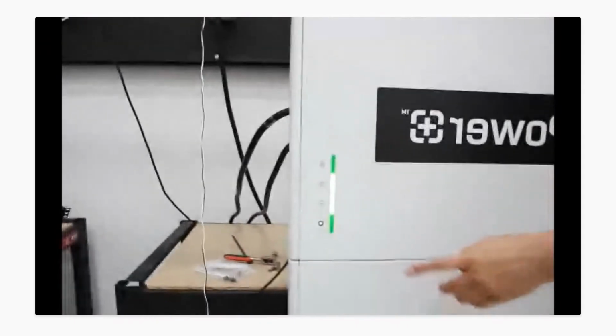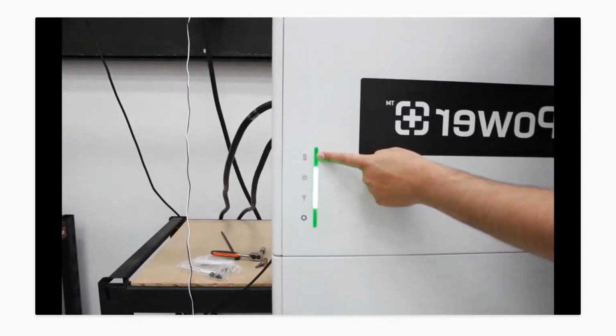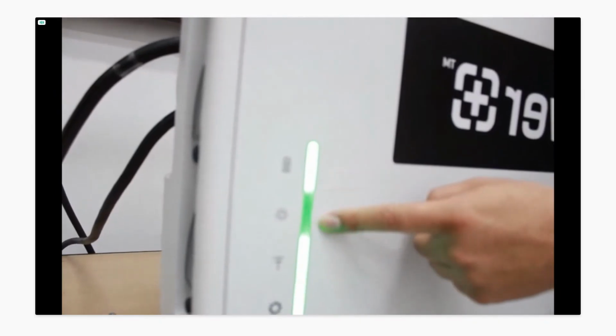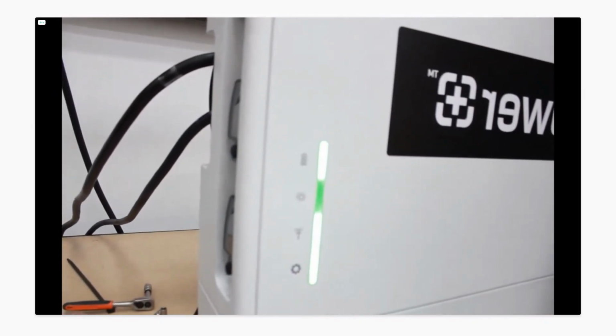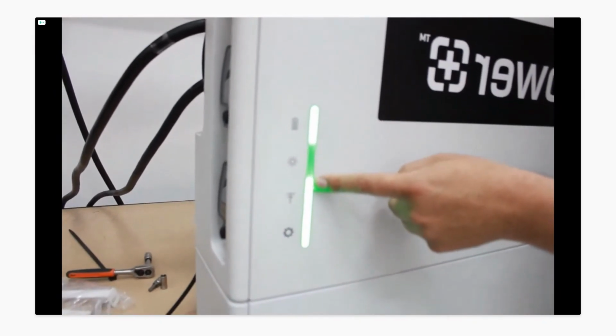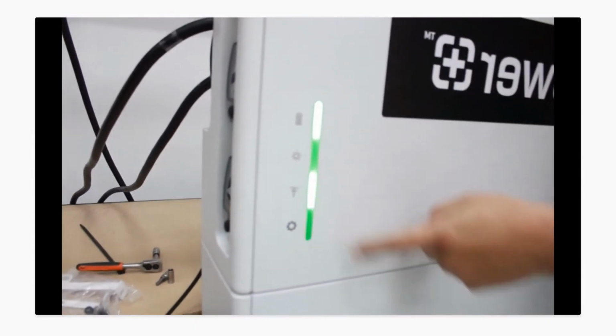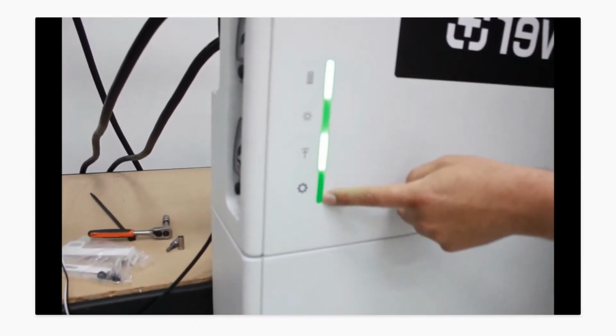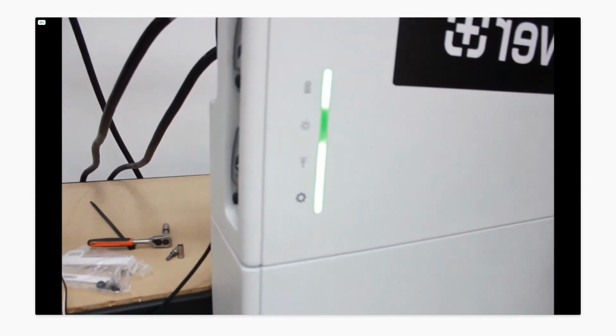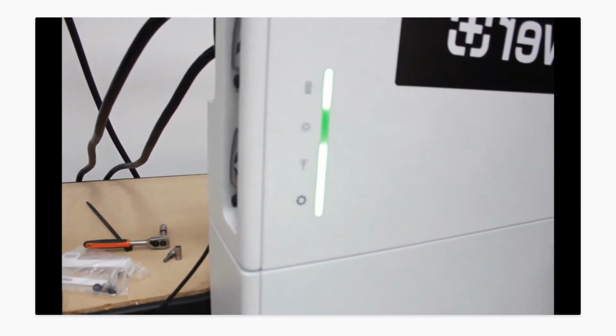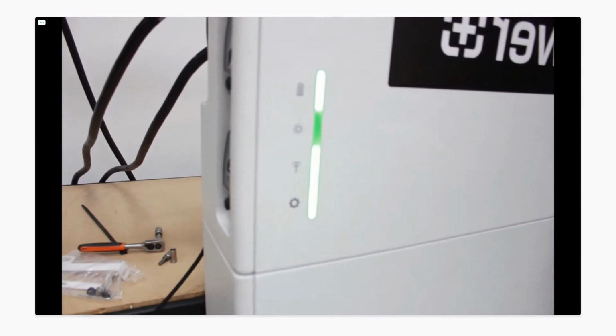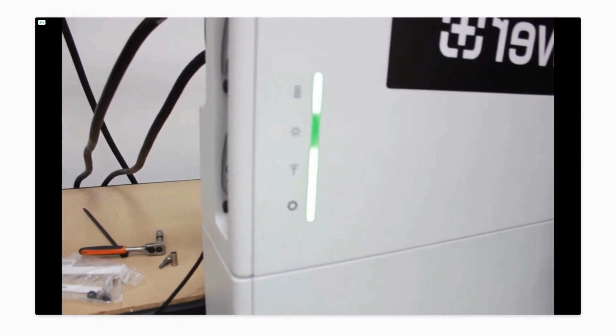Now these LEDs here show us a few different things. The top LED is the battery, so the battery is going to synchronize. This one is solar, it's turned off, meaning there's no solar connected. This is the grid connection, telling us the grid is there. And this flashing light is the system checking to see if an energy meter is there. Once it's solid, which it is now, it's very happy with us. So it's found our energy meter.